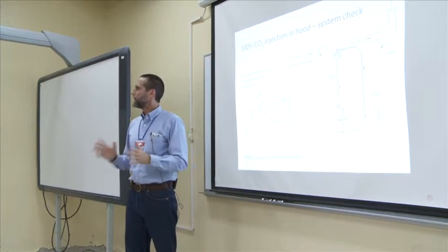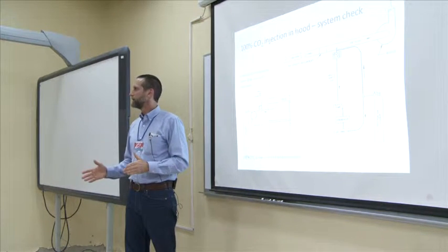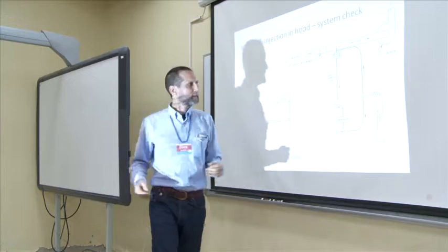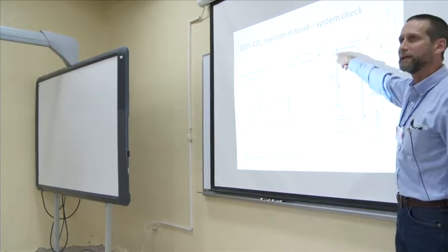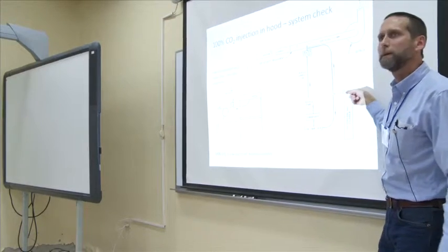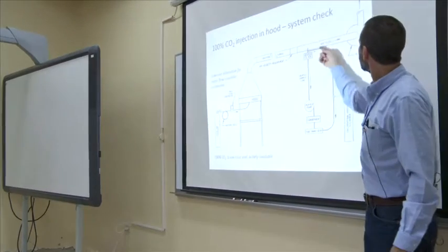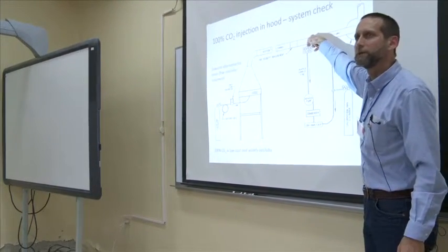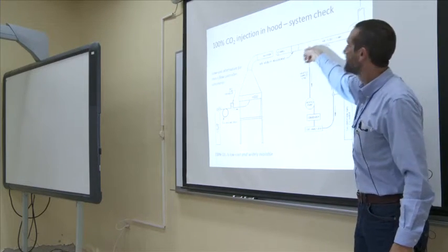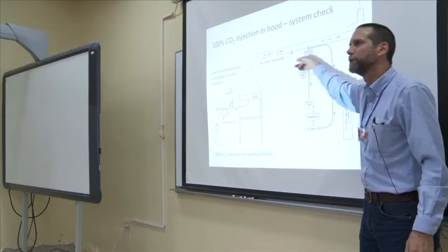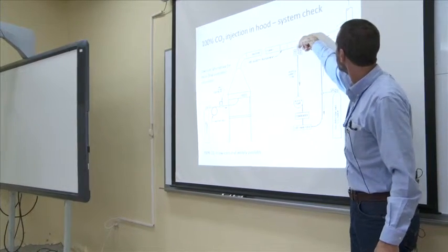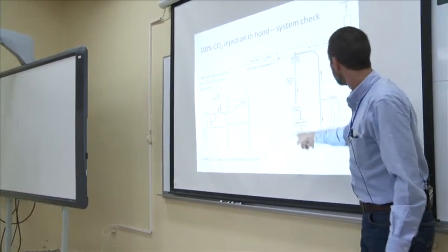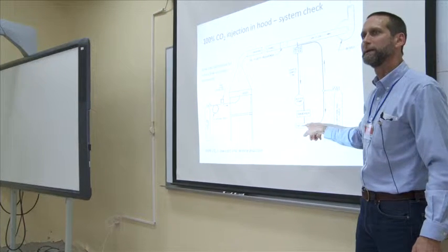We were following the EPA method to the letter, but it turns out that when you pressurize, this was leaking. So when we were calibrating, we were shooting the calibration gas in here under pressure, and it was leaking out. It was coming out through the leak here in the heated filter. Okay, so the gas was coming out, and we were still getting the correct measurement, right?